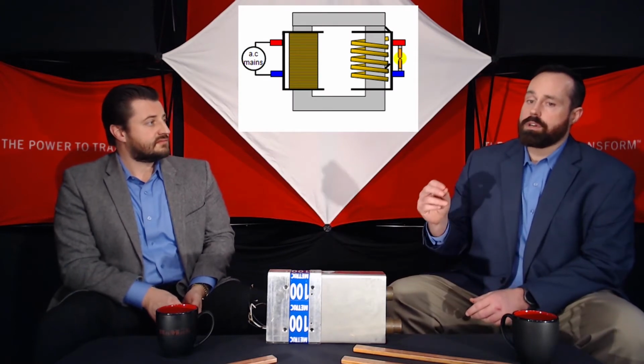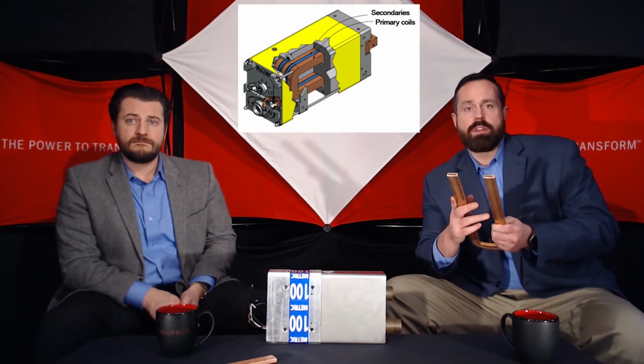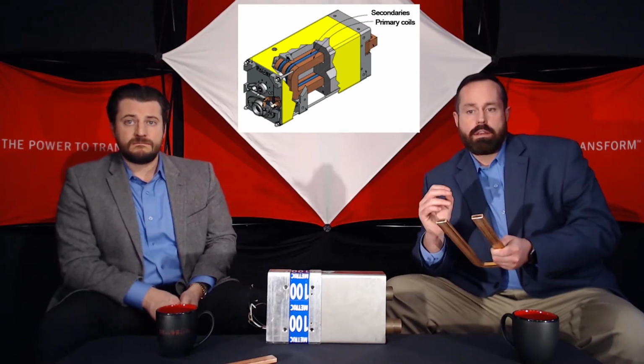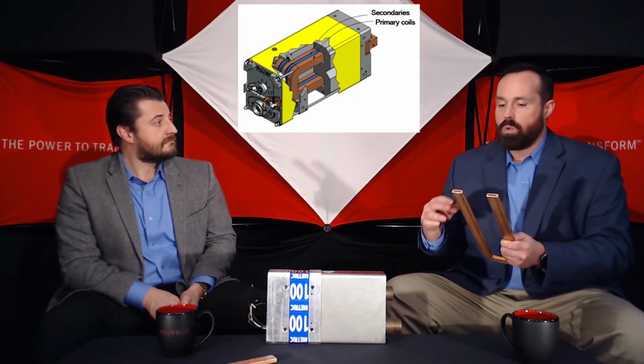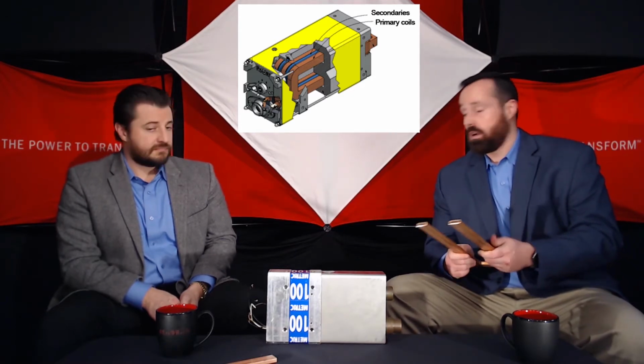Wow, that sounds like some pretty significant improvements in efficiency over other types of cooling systems. How does it actually work, though? So in a transformer, which we have here, there are primary and secondary coils. The secondary coil is fewer turns, as shown in this image. As you know, electric current is what creates heat by Joule's law, or I squared R. We have designed our water-cooled transformers with a channeled bus bar in the secondary, the high current, high heat component of the transformer. So as you can see here, we have this channeled bus bar. Now, this is what's delivering the higher current to the secondary, and it's quite an ingenious way that we actually plumb water through the hottest portion of our transformer.